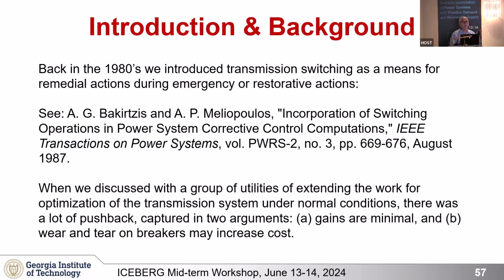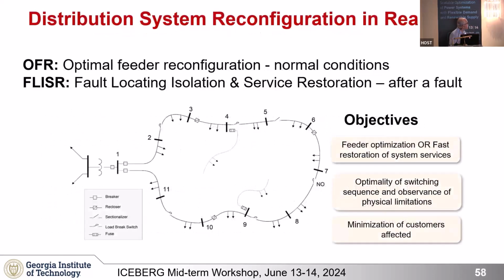However, for distribution systems it makes a big difference, and everybody does that. In an active distribution system we need both optimal reconfiguration of the feeder and also the problem known as FLISR. When there is a fault, we have to reconfigure the system to minimize the customers affected, and this has to be done in real time whenever there is a fault on the distribution system.